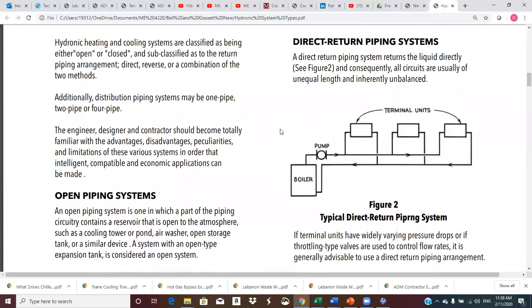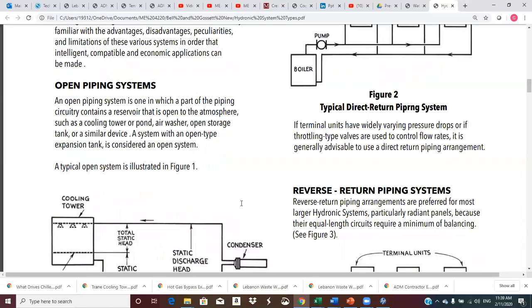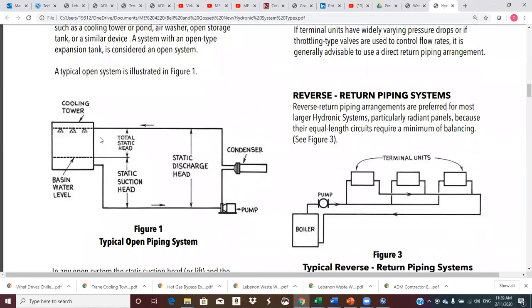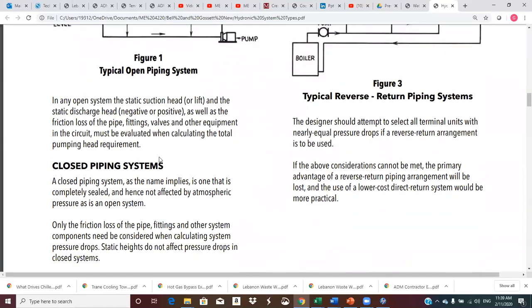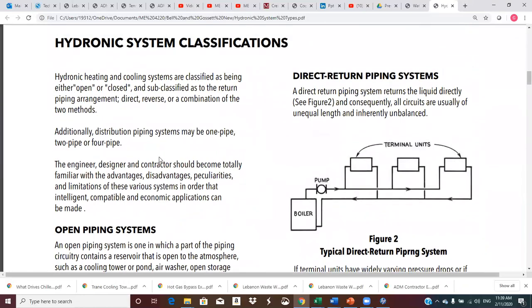So this could be an example of a closed system. So the boiler, everything is encased in piping and components. We come out of the boiler, all of this goes through coils, piping, return. So it just pumps around in a circle. There's no break in the system where the pump has to pick water up from this level and put it up here. So this would be an example of the closed piping system.